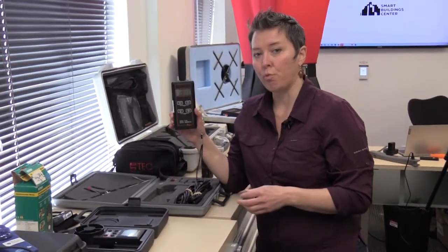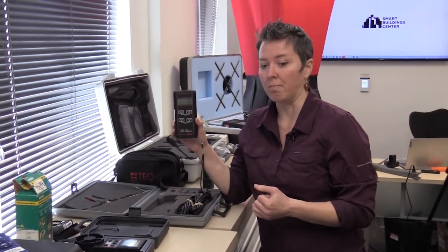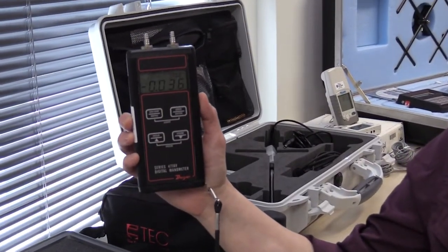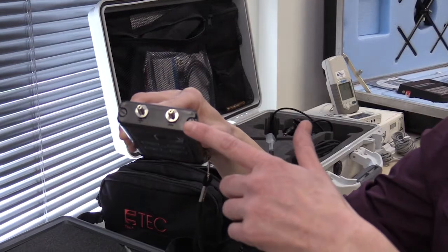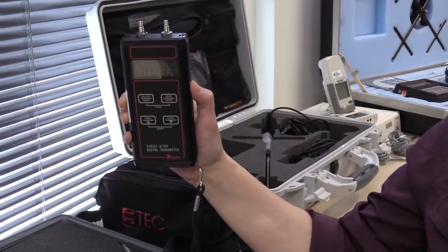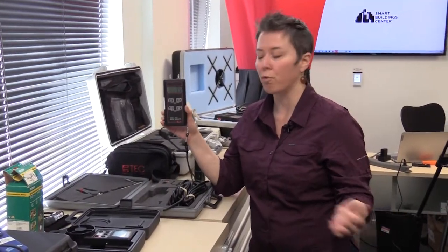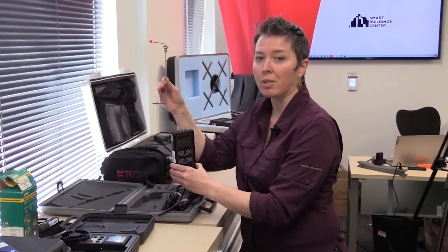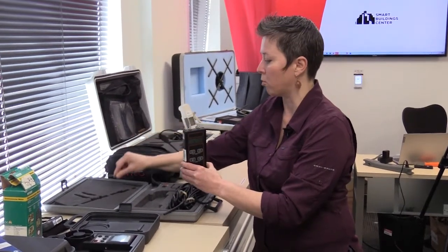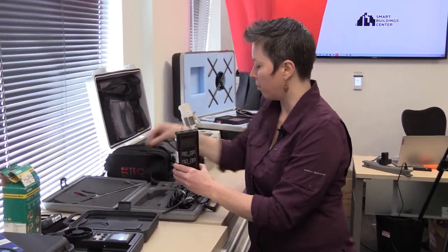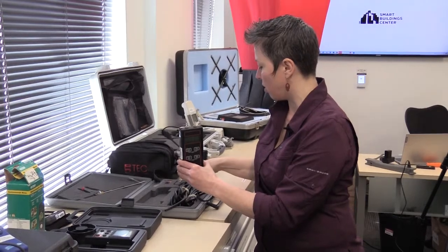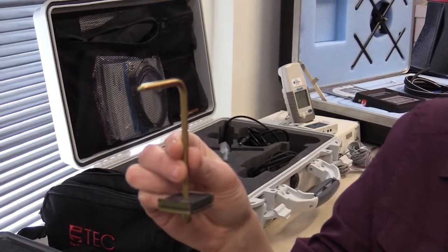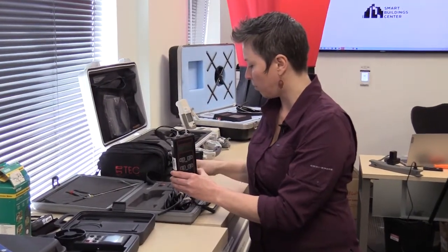So this measures pressure differential and total pressure. And this has a couple of little ports on the top here, some tubing. You connect the tubing. You can either leave the other end of the tubing open to measure room pressure, or you can connect it to a pitot tube. This is another pitot tube. This is a small version. This is much more compact and portable. This also includes some duct static pressure probes. So similar, these go up into the duct and measure the static pressure.